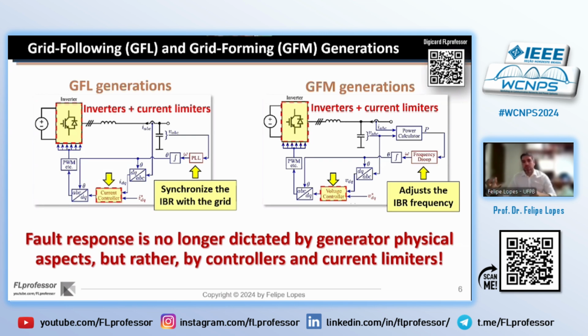So if we consider the current limiters and also the controllers, the action of the controllers, the fault response, we can say that the fault response is no longer dictated by the generator physical aspects that we used to see for synchronous generations, but rather the controllers and the current limiters will dictate how these generations will respond to fault scenarios.